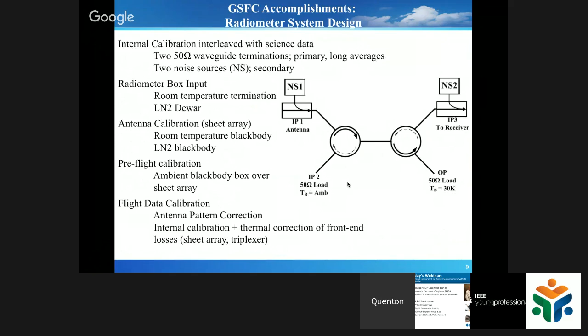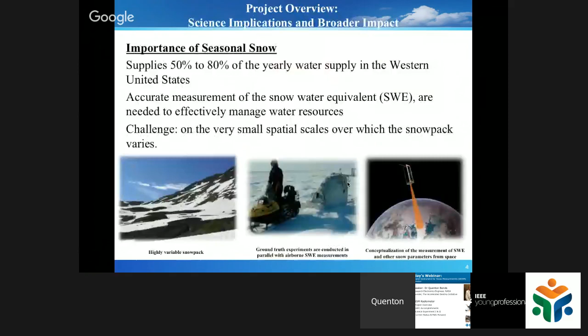You can form a straight line between those two and calibrate the noise sources, because the noise source is going to provide a brightness temperature and a voltage. And based on your calibration line, more than likely your snow measurement will be between, you'll get a voltage out between the voltage and the respective brightness temperatures of your calibration loads. And you can just use the equation of a straight line to get the actual brightness temperature based on that voltage. That's the easy part. But the hard part is when you have a bunch of loss in the front end, which we do. So then you have to develop a model of your complete front end, a mathematical model of every component in your front end, which I really don't show in this presentation. But this is kind of a general overview.